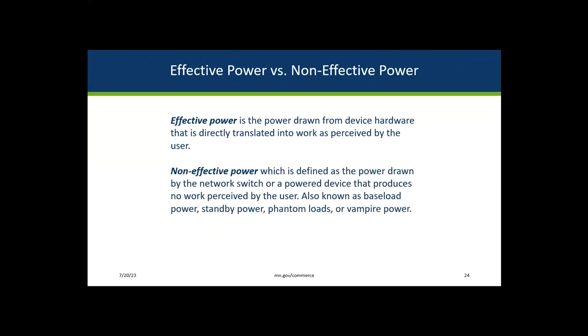Based on this, we can define two types of power loads for intelligent building technologies: effective power and non-effective power. The effective power is the power drawn from the device hardware that is directly translated into work as perceived by the user. In this example, the light emitted by the classroom fixtures. The non-effective power is the power drawn by the devices that bring intelligence and network capabilities to the lighting system. This power produces no work perceived by the user.